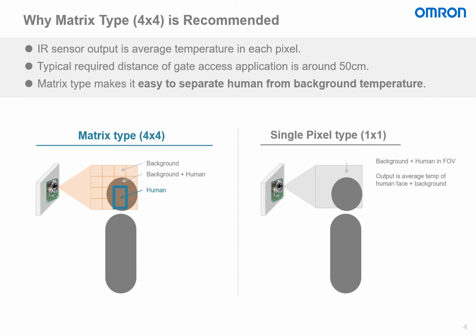In the display below, we have the matrix type versus the single pixel type. In the matrix type, we have 2 cells out of the 16 that have the entire human body temperature that can be read. Therefore, the other cells can be ignored. However, in the single pixel type, the output would be the average temperature of not only the human face, but the background objects as well. So the customer, in this case, would not be able to get a clear reading of the temperature of the human body.